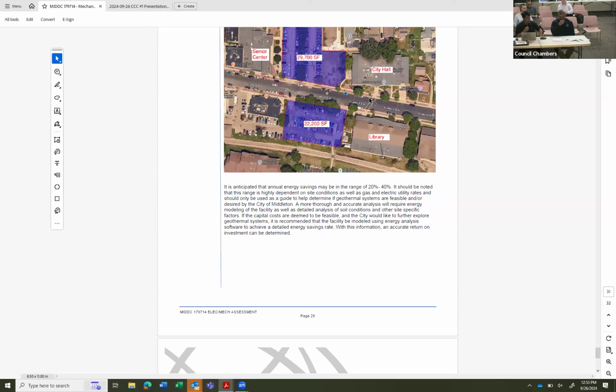It would be a closed system, so there would be a glycol loop that would go from the heat pump in the basement to the geothermal field, and then there'd be the condenser and heat exchanger within the heat pump that would generate hot and chilled water to distribute throughout the building, and it would all be closed systems.